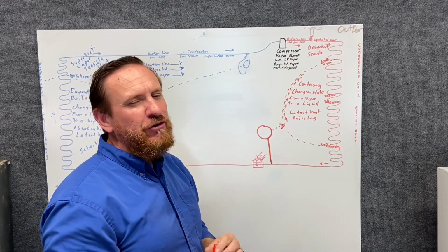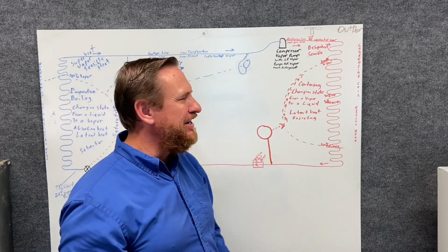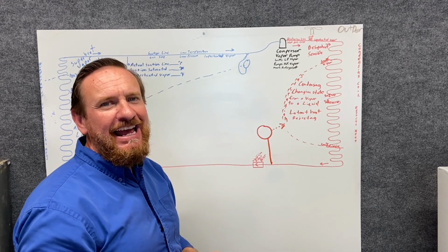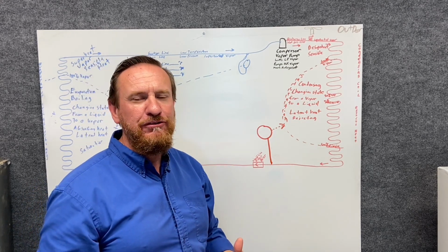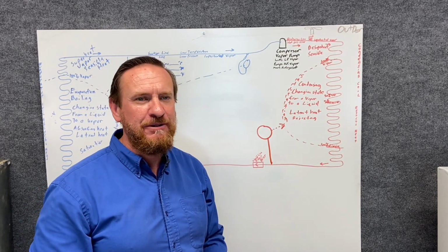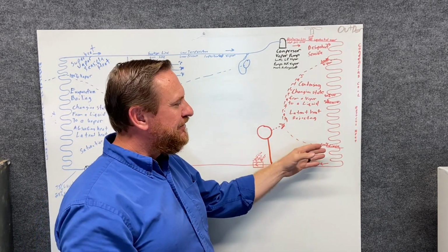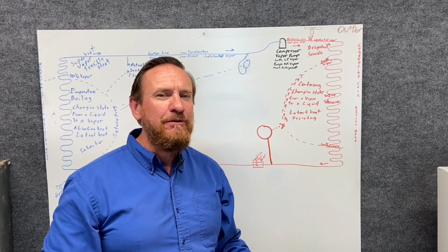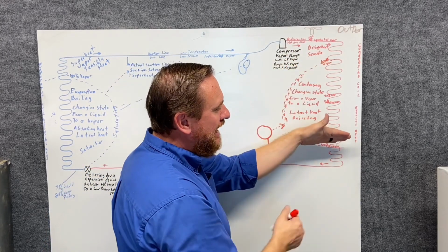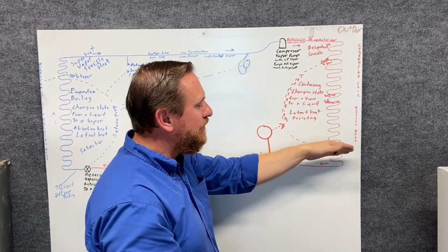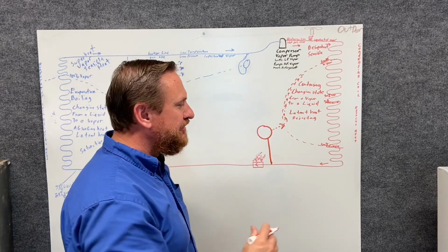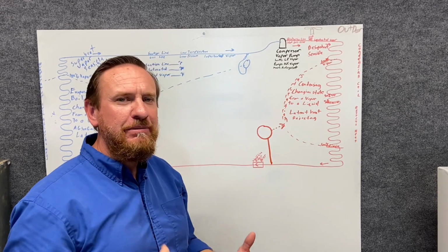So there's a new vocabulary word that we have to learn and a new definition, and this is subcooling. Subcooling is defined as a sensible heat removed or rejected from a substance below its saturation. Subcooling, the amount of sensible heat rejected from a liquid below its saturation point. So here's my saturation point. I'm still taking heat away from this liquid, so it's now subcooled liquid. It's a subcooling effect. So the very bottom side of this condensing coil is going to be subcooling.